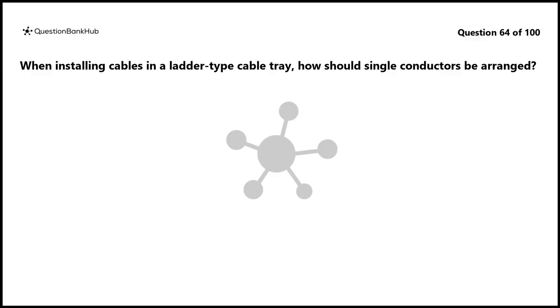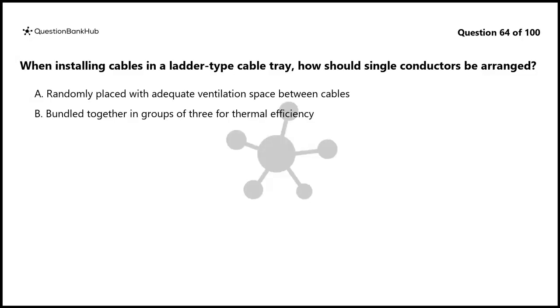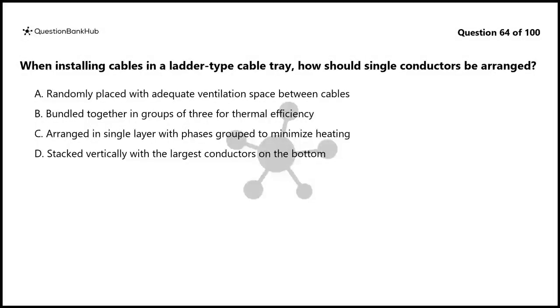Question 64. When installing cables in a ladder-type cable tray, how should single conductors be arranged? A. Randomly placed with adequate ventilation space between cables. B. Bundled together in groups of 3 for thermal efficiency. C. Arranged in single layer with phases grouped to minimize heating. D. Stacked vertically with the largest conductors on the bottom.